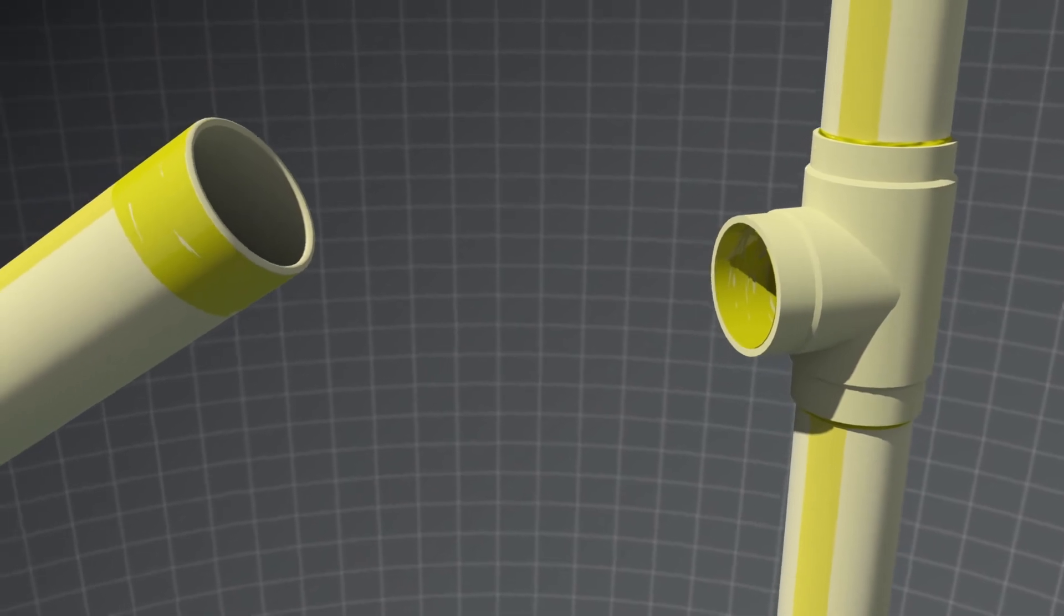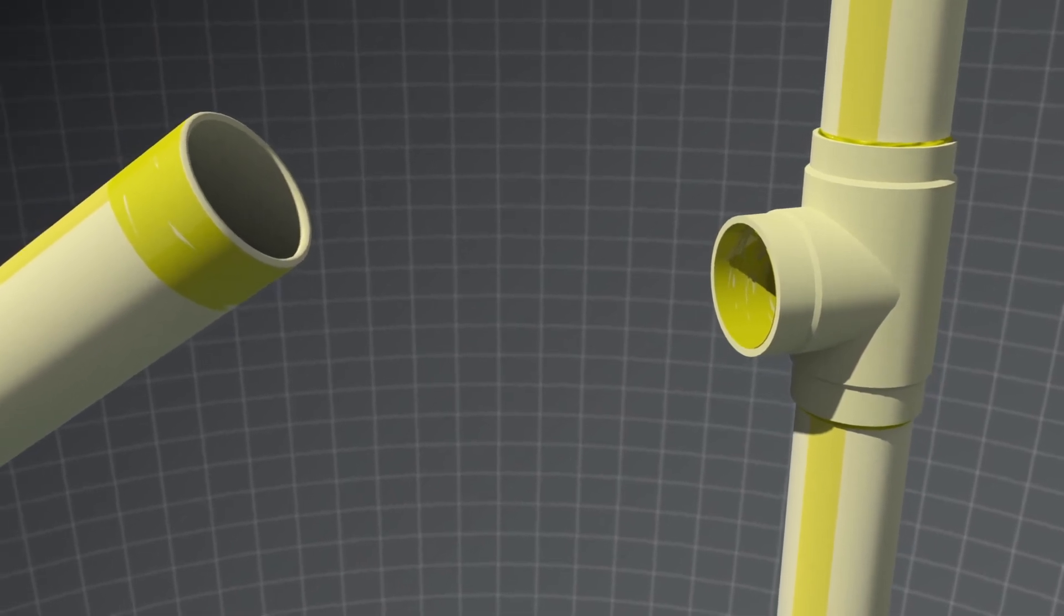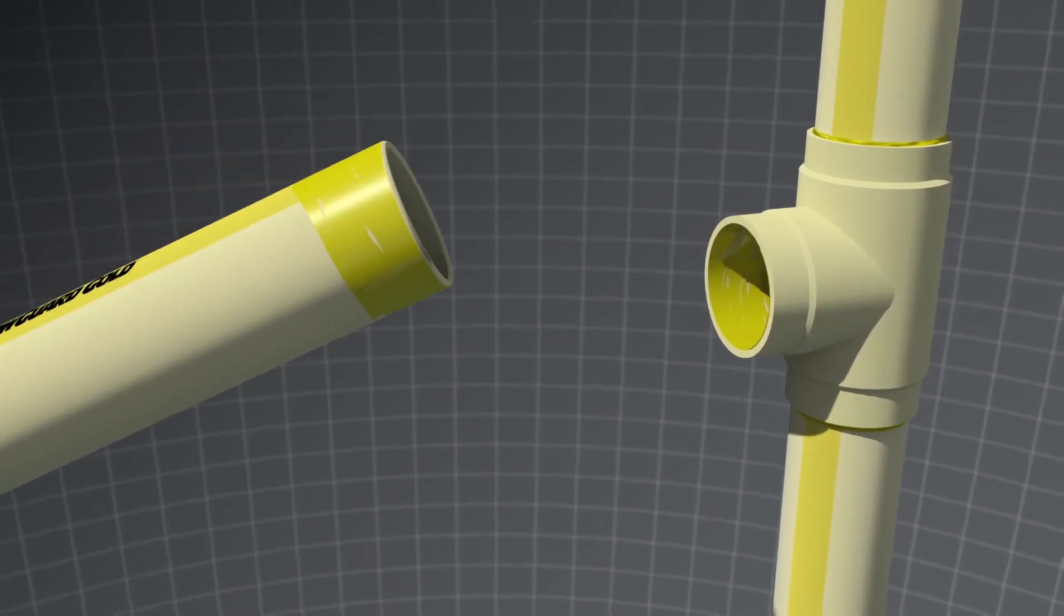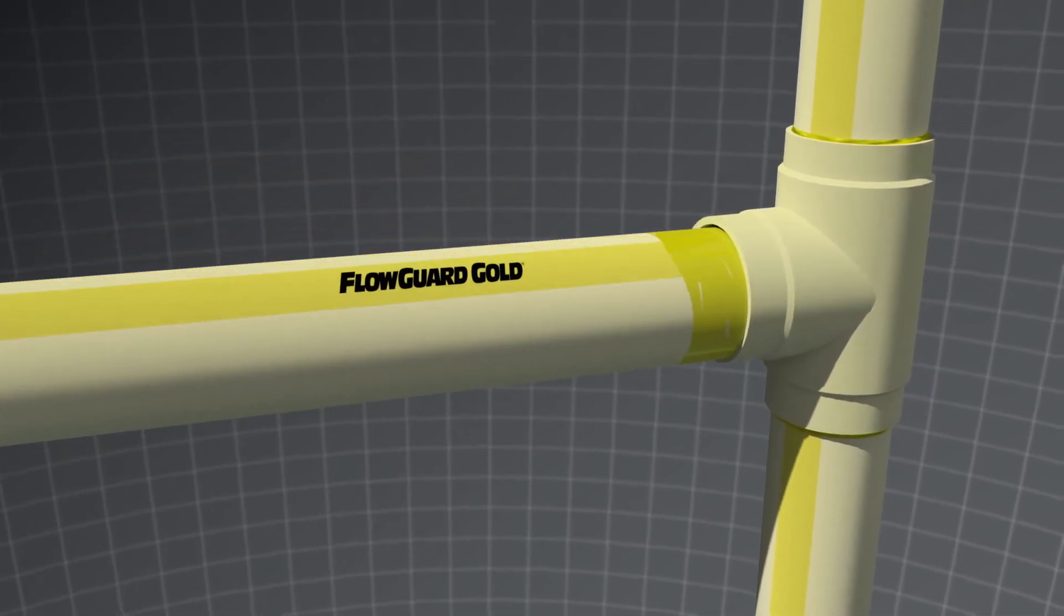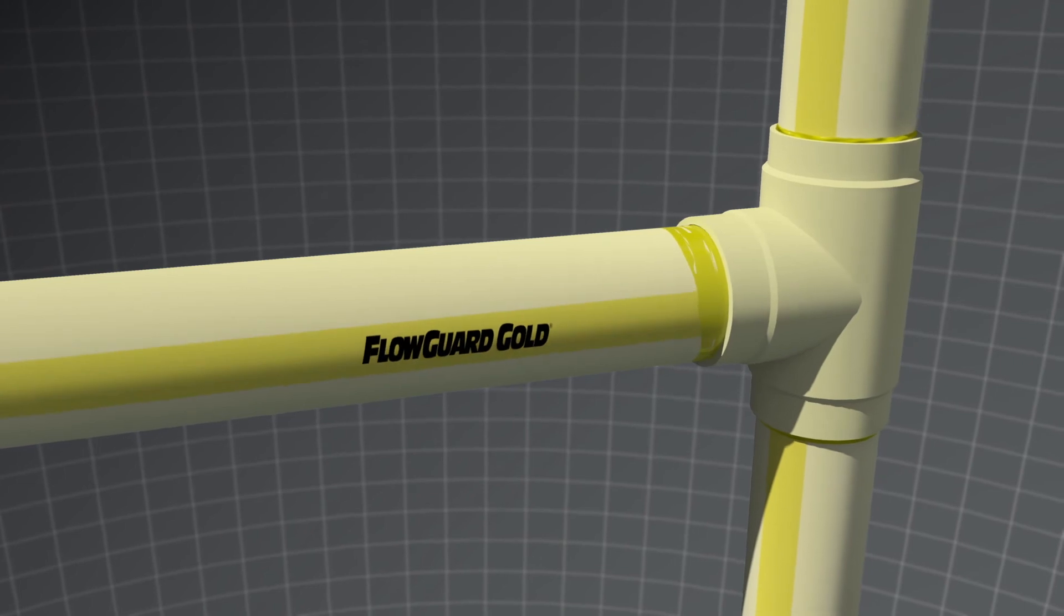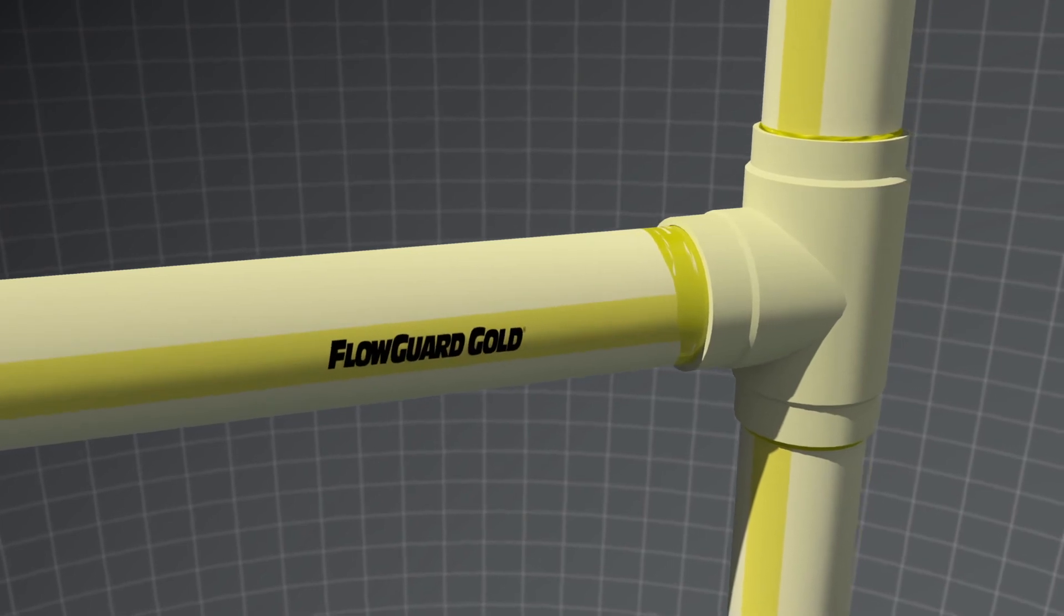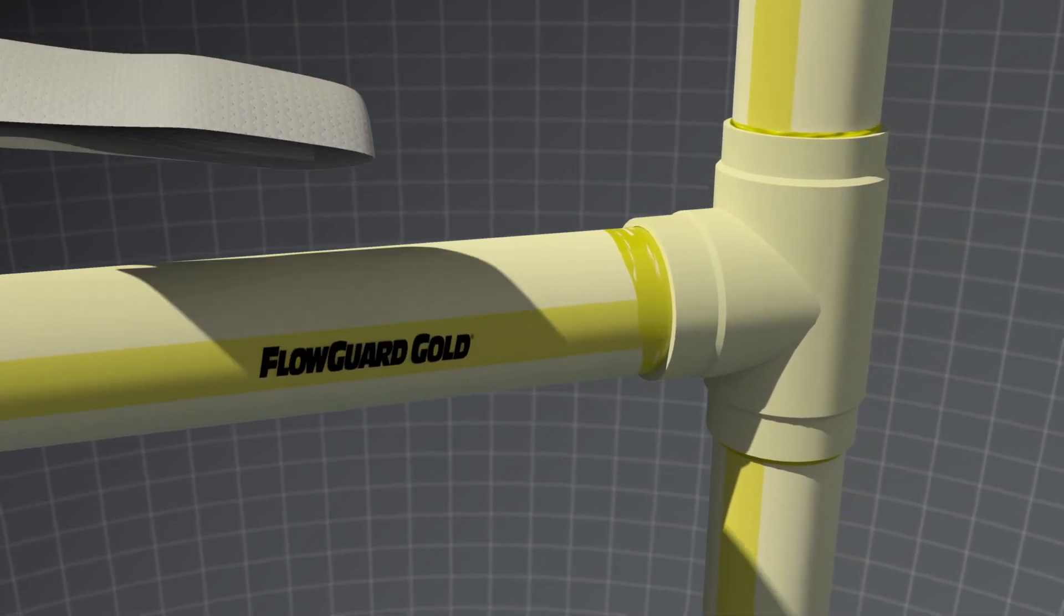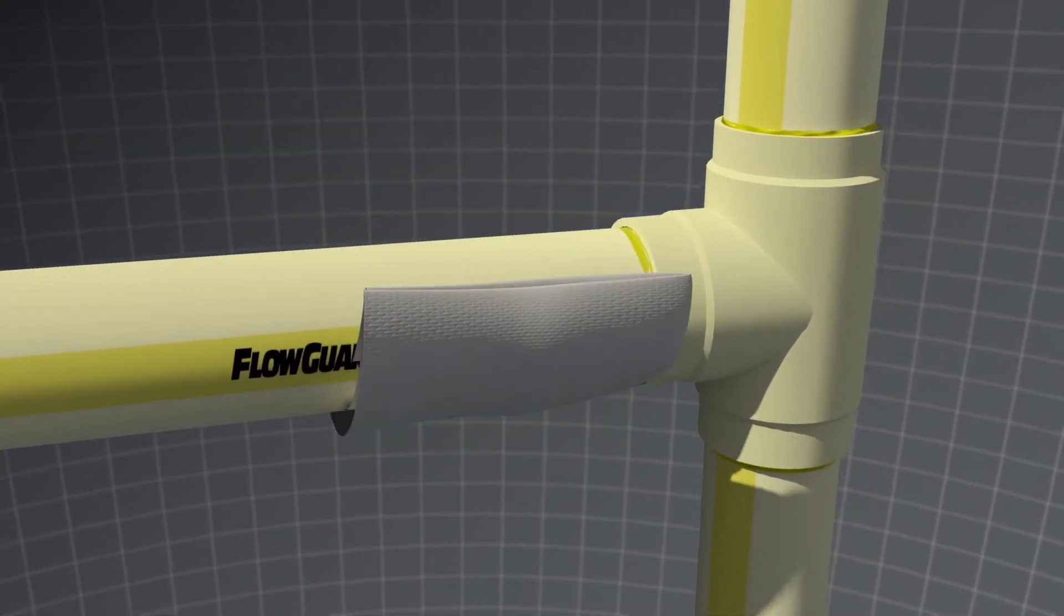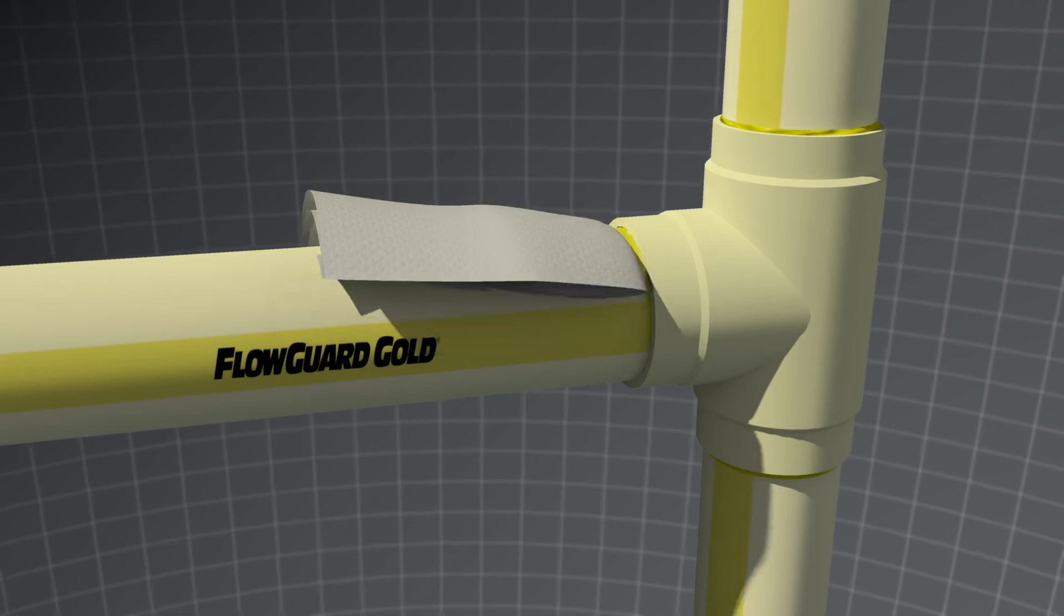Next, insert the pipe into the fitting while turning a quarter turn or approximately 90 degrees. Hold for 30 seconds to allow the joint to take. Wipe excess cement from the outside of the pipe.